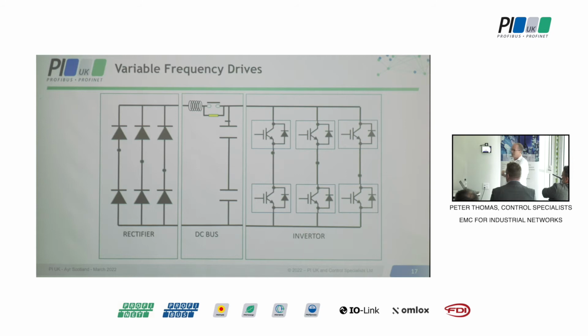There's a rectifier section to convert the incoming AC into DC. There's the DC bus section, which smooths it to give us a constant voltage in the order of about 600 volts. And then there's the inverter section, which consists of high power switching transistors. On the left, we're going to feed it with a 415 volt AC supply, so no big deal here.